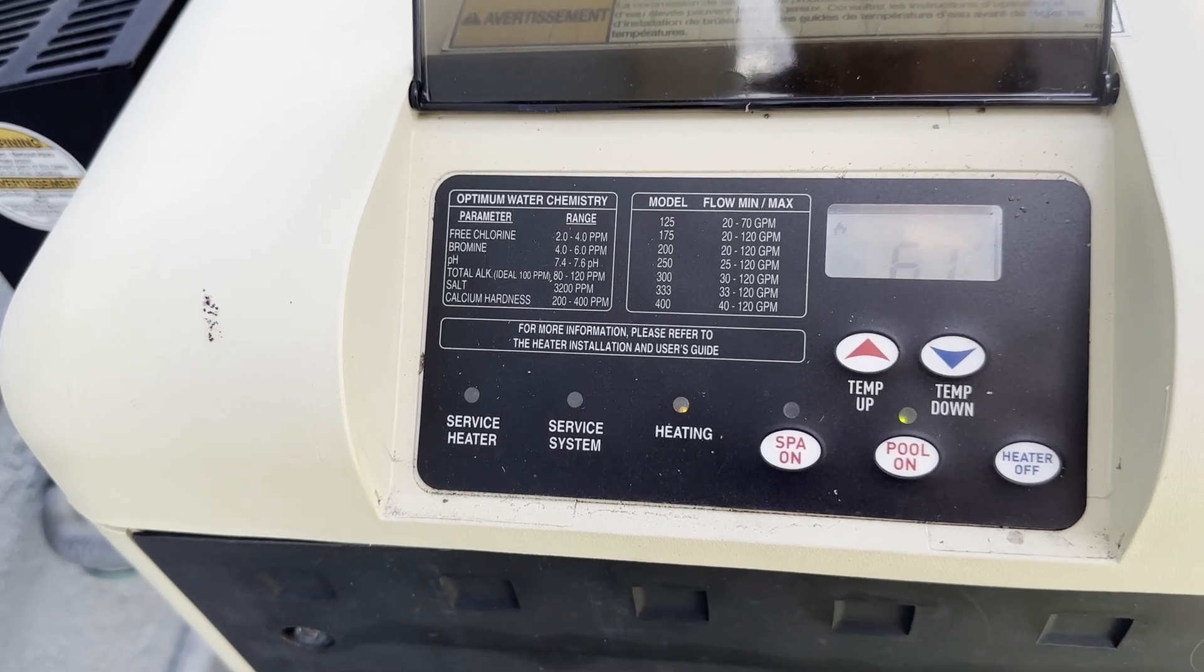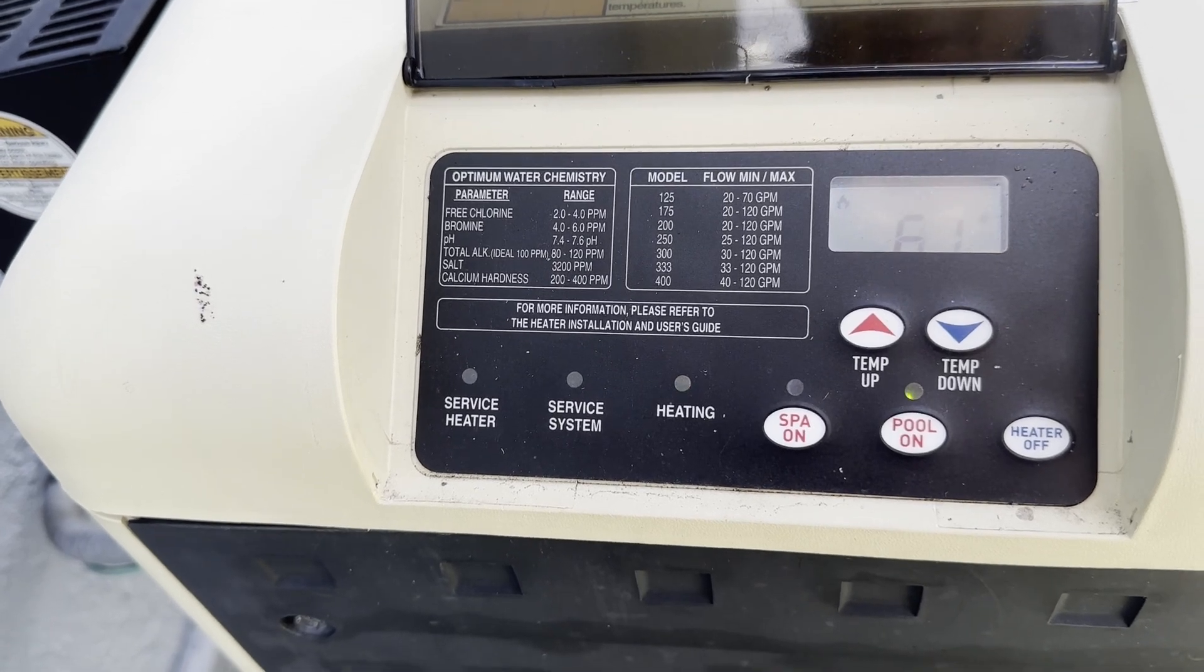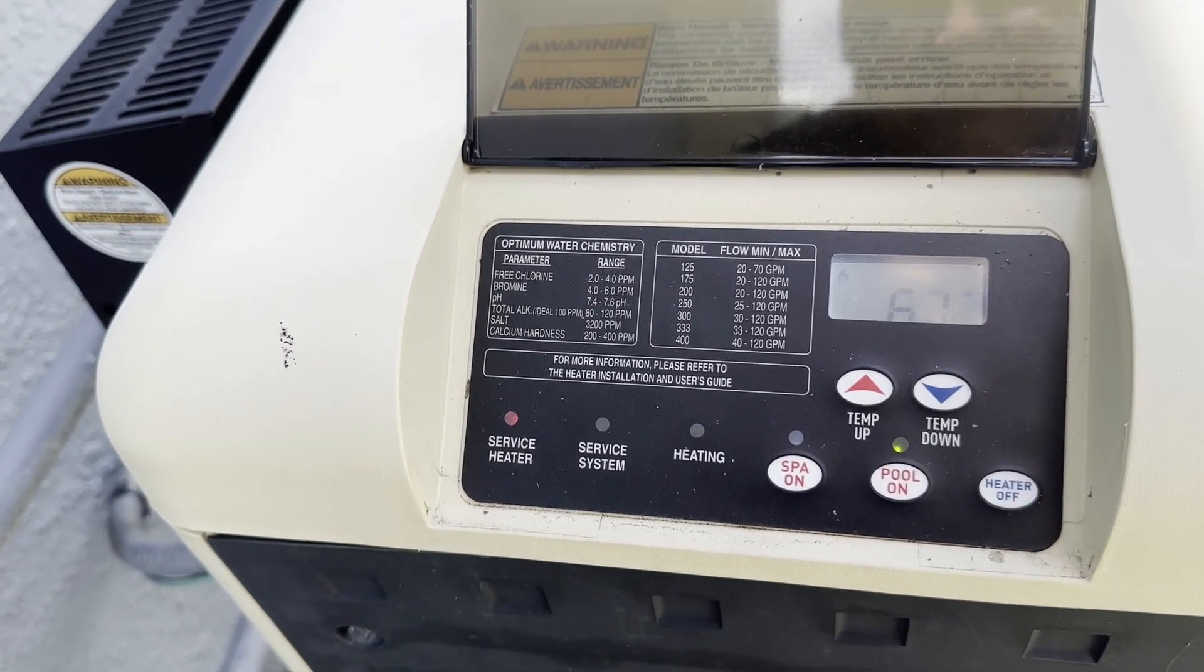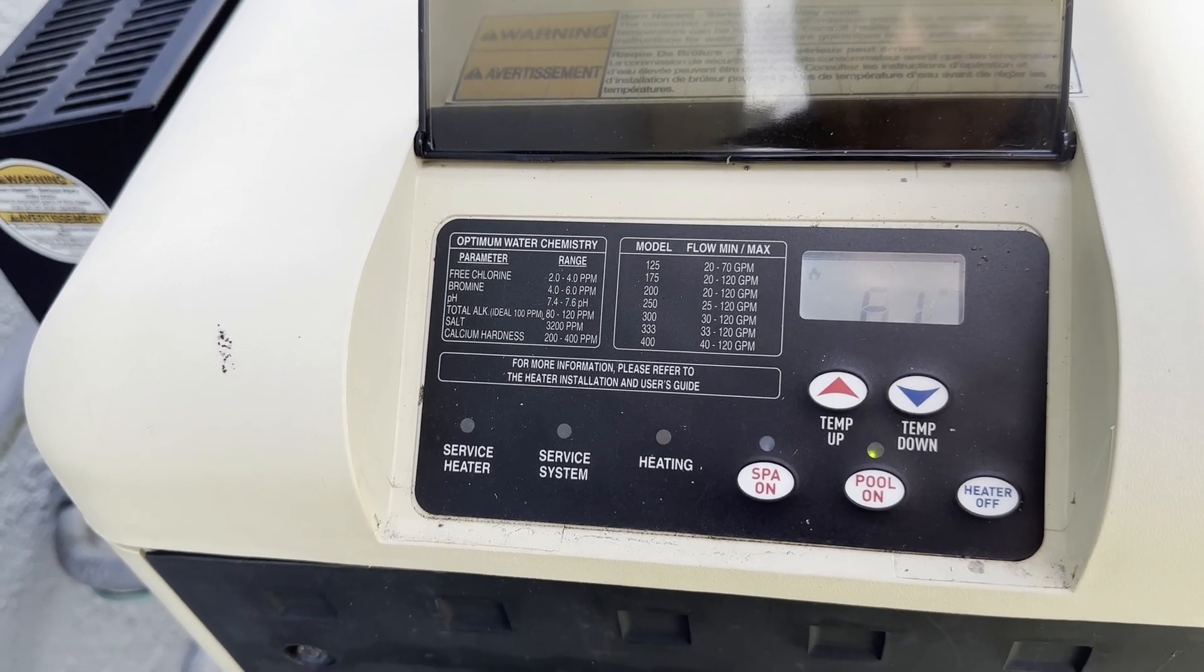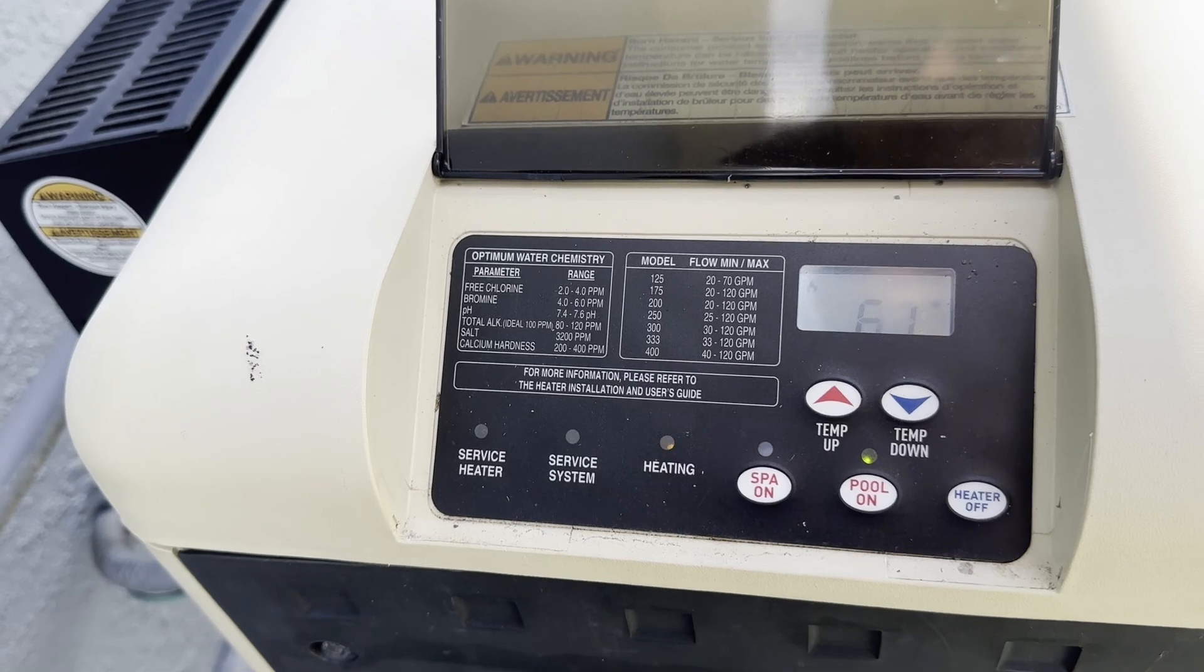Turn it on. And the light is flickering that it's heating, but there's no hot air yet. It takes a while. The igniter has to ignite, has to glow, has to get hot enough, and then a flame will ignite the gas. And then the gas will flow through it and start heating. When we're not getting anything, usually you'll hear a click from the gas valve, which is in the back. Still no heat, still no ignition. You'll definitely hear it when it kicks on.